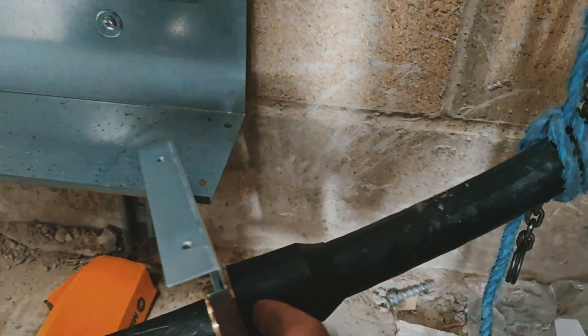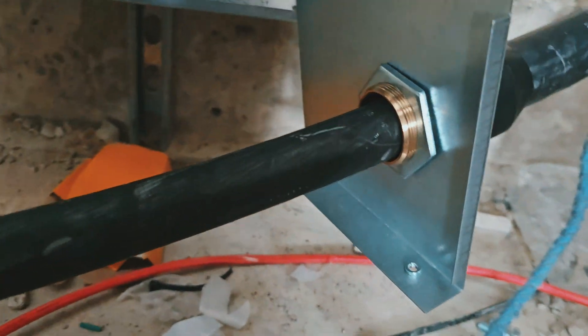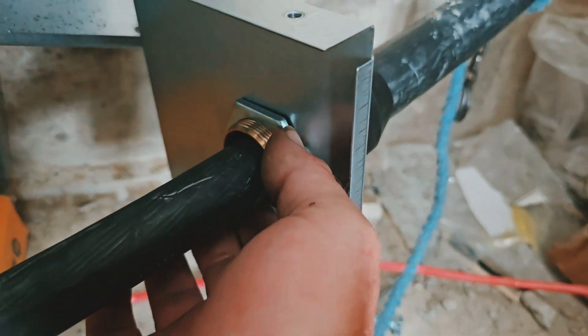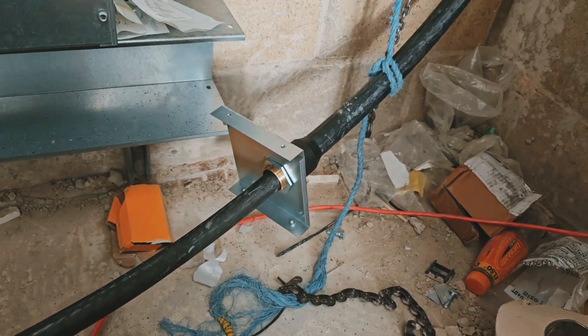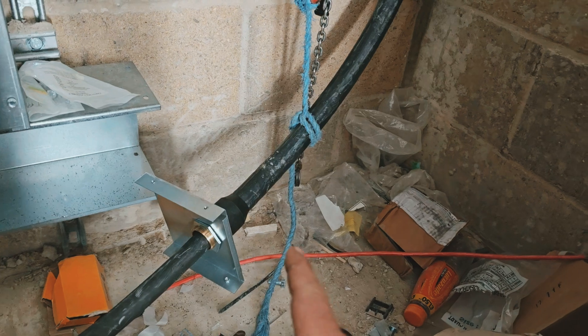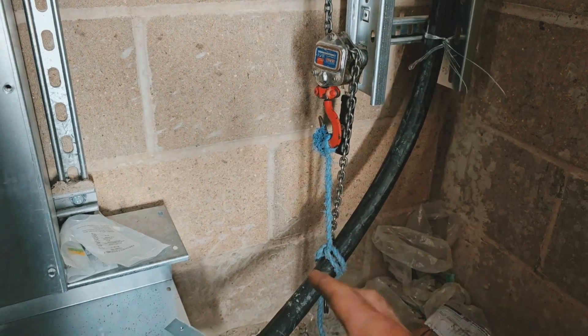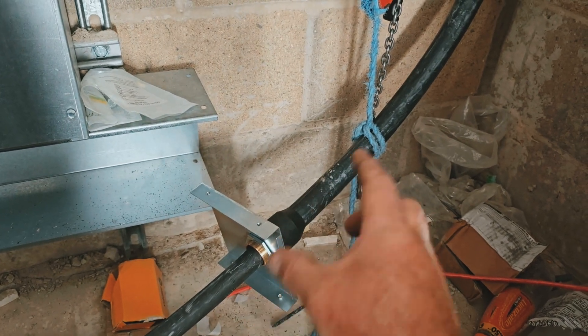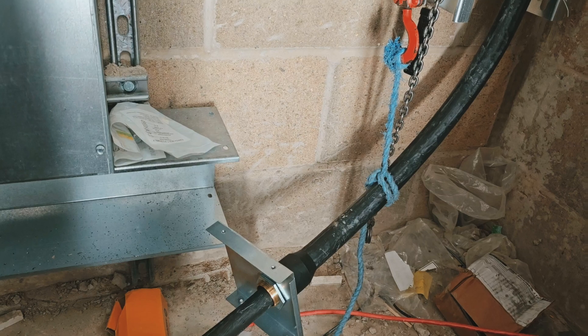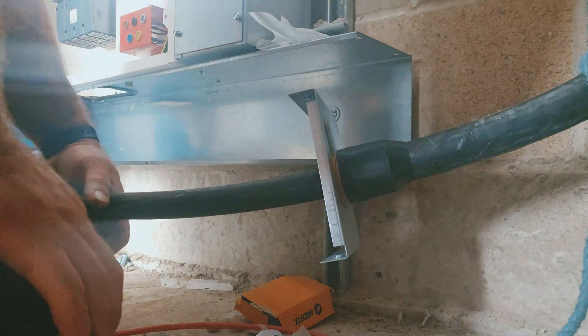So this is what we're left with — there's the banjo. I need that to finish at the top when I'm done so I can get a drill in, and then the end cap of the trunk and the lock nut. Now the lock nut is loose — it's holding the gland but holding it loose. I've got to get that lifted up. This is where the little ratchet puller comes into play, because I can move it in increments and still work with two hands.